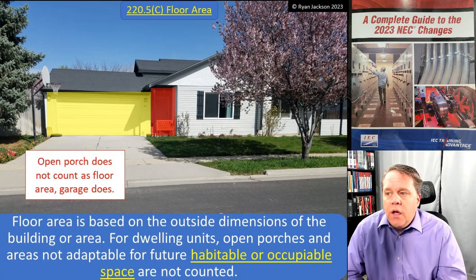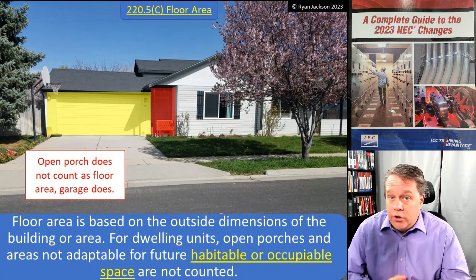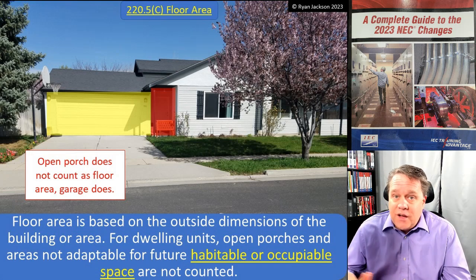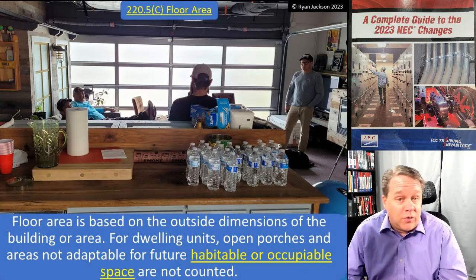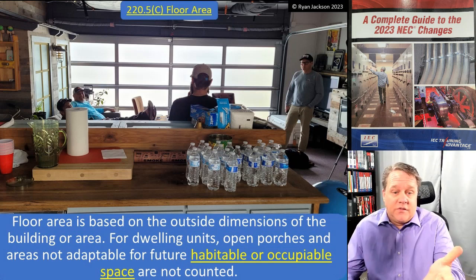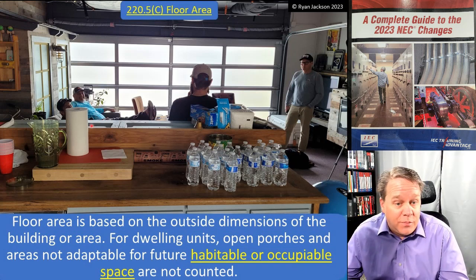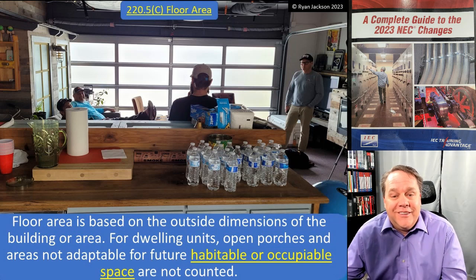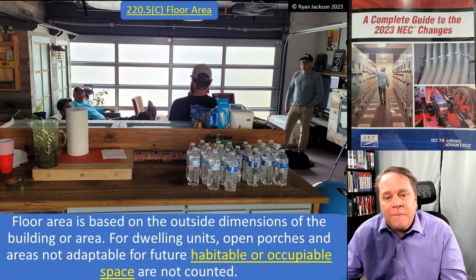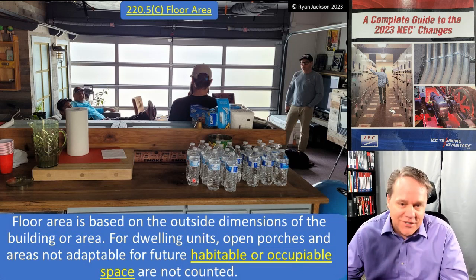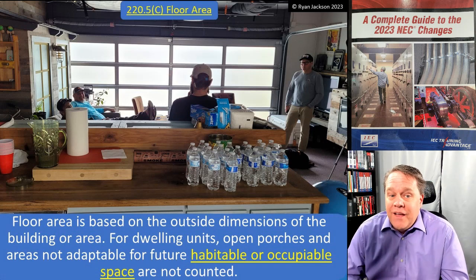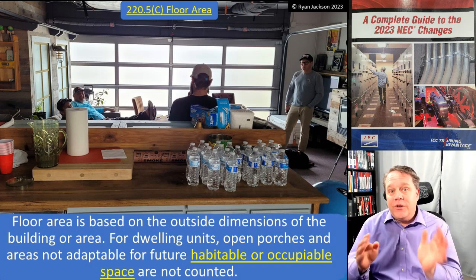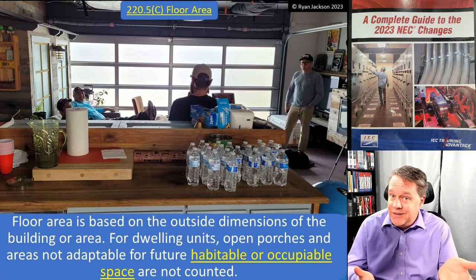If your garage is an actual garage and that's all you're ever going to do with it, maybe 3 VA per square foot is excessive — but I'd argue it's not. You're going to have lights and convenience receptacles in the garage. And a garage today can be a man cave tomorrow. I stopped by an electrical contractor's house in Park City, Utah and put on a little code class — ended up with like 15 guys in the room. They had a couple of LED TVs, a full bar, a full kitchen — and it was a garage.